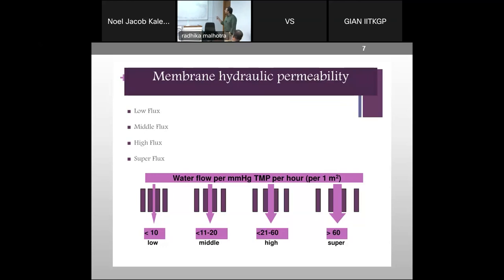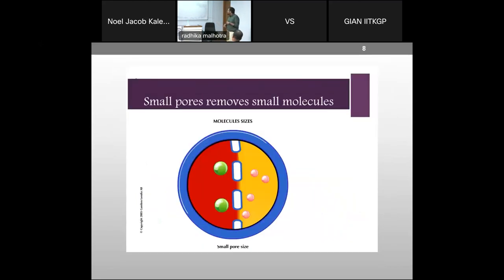But all membrane manufacturers are trying to move to high flux. That is anywhere above 20 ml per mmHg per hour per meter square. So that much water removal rate. If your membrane has very small pores, it will remove small metabolites like urea and creatinine, which are less than 500 Daltons.